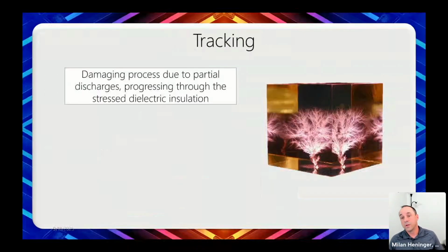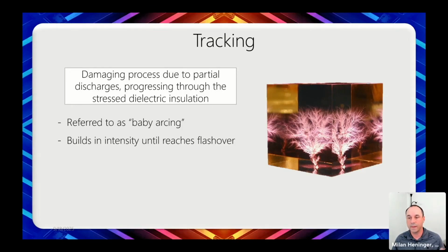So tracking. Tracking is the damaging process caused by those partial discharges, and it's progressing through a stressed dielectric of some insulation. Some people refer to this as baby arcing, but what we experience here is that it's building in intensity and then it flashes over. It usually requires dirt, contaminants, moisture, or workmanship defects, like stress cones where you cut too deep and don't sand everything off. But you need some path for the electricity to travel along.